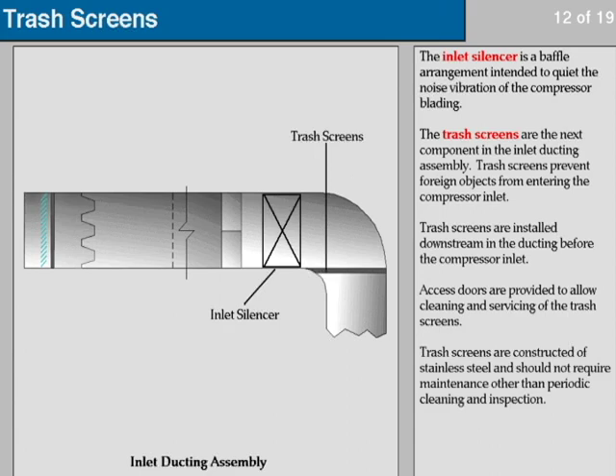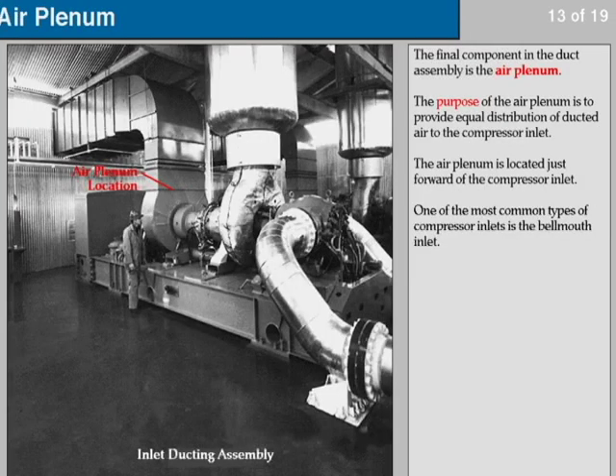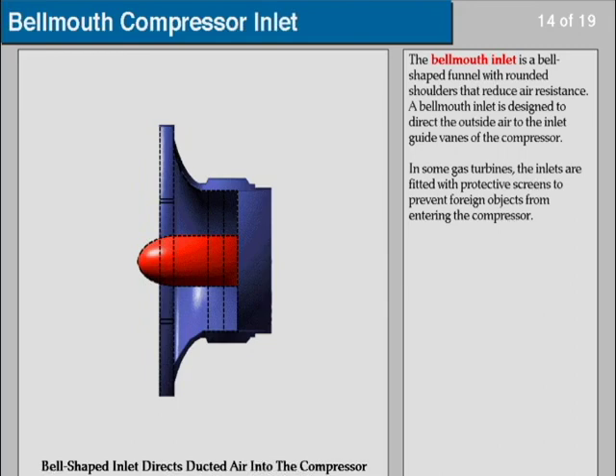Trash screens are constructed of stainless steel and should not require maintenance other than periodic cleaning and inspection. The final component in the duct assembly is the air plenum. The purpose of the air plenum is to provide equal distribution of duct air to the compressor inlet and is located just forward of the compressor inlet. One of the most common types of compressor inlets is the bellmouth inlet, which is a bell-shaped funnel with rounded shoulders that reduce air resistance. A bellmouth inlet is designed to direct the outside air to the inlet guide vanes of the compressor. In some gas turbines, the inlets are fitted with protective screens to prevent foreign objects from entering the compressor.